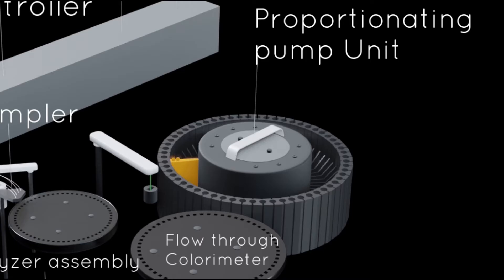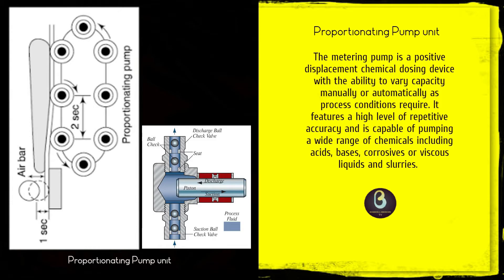The pumping technique involves the peristaltic action produced by a series of rollers passing along an array of parallel plastic pump tubes. Each roller compresses all tubes so that the rate flow in each tube is proportional to the square of the pump tube diameter. Color-coded tubes with a range of nominal diameters and pumping rates are available in three materials.